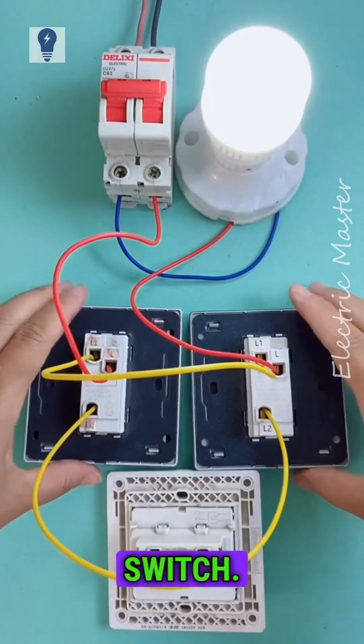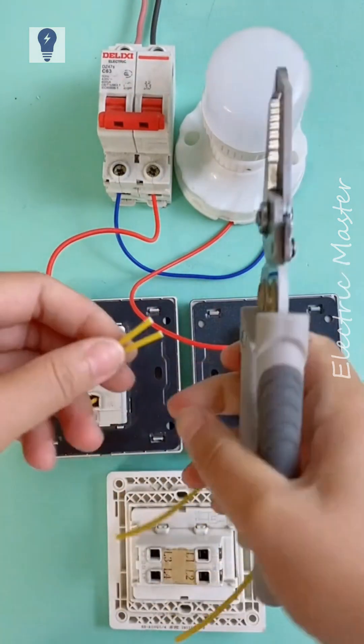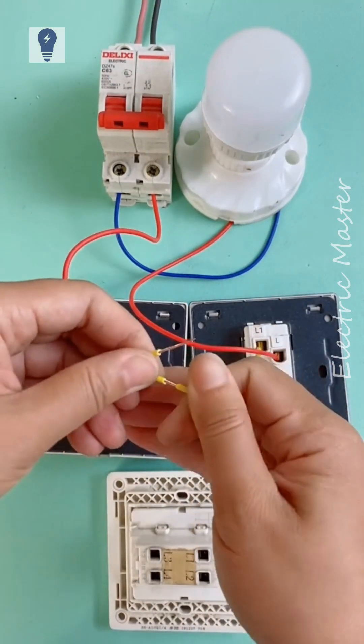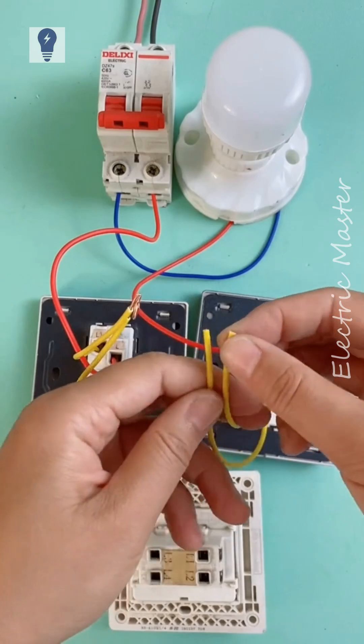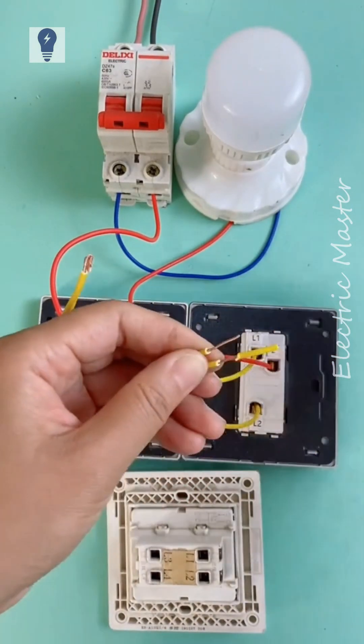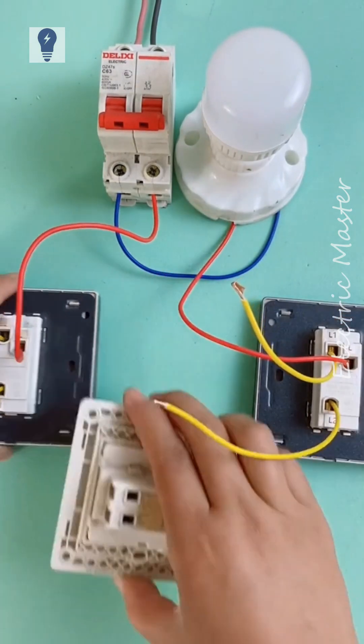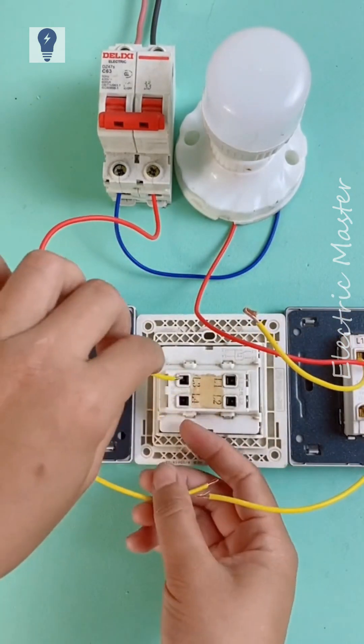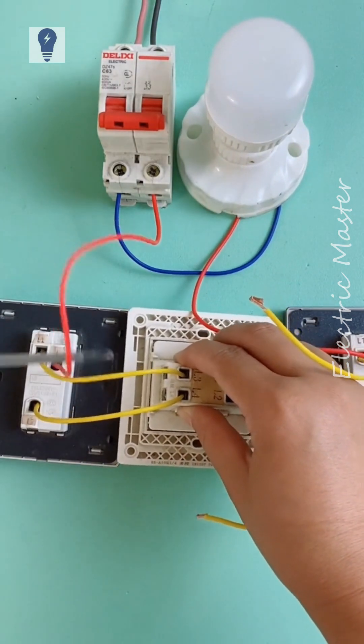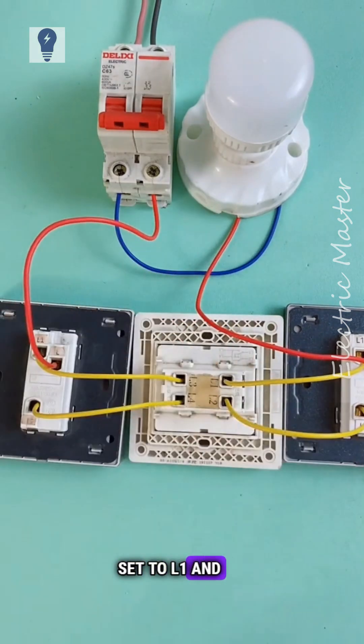Now let's prepare an intermediate switch. Cut the double wires. Connect one set to L1 and L2, and connect the other set to L1 and L2.